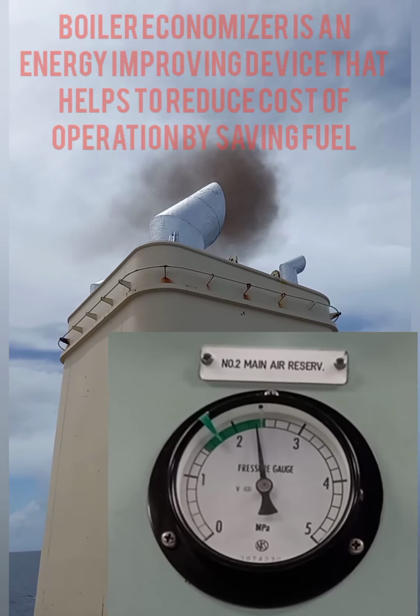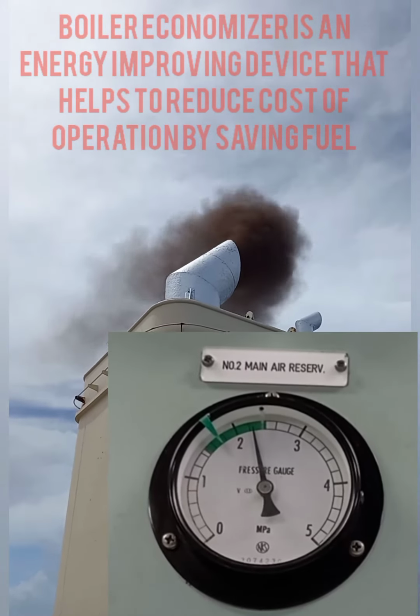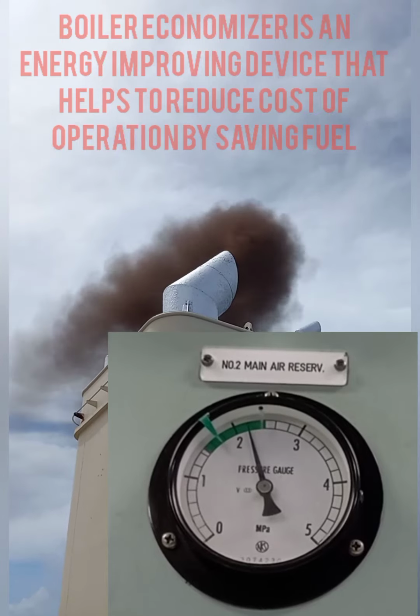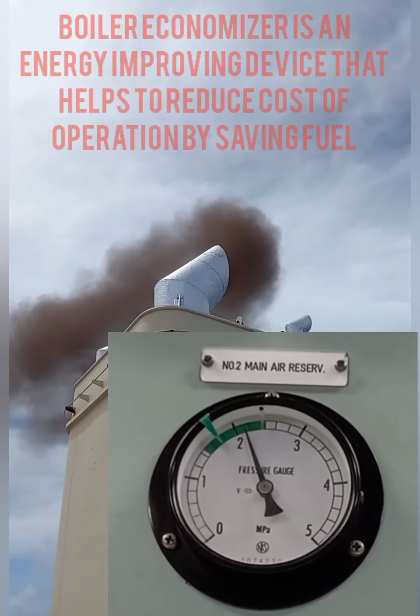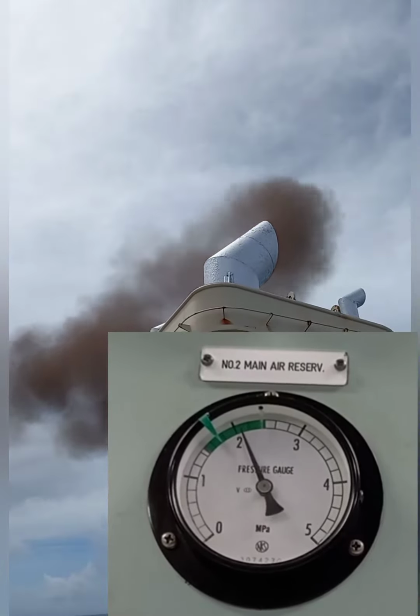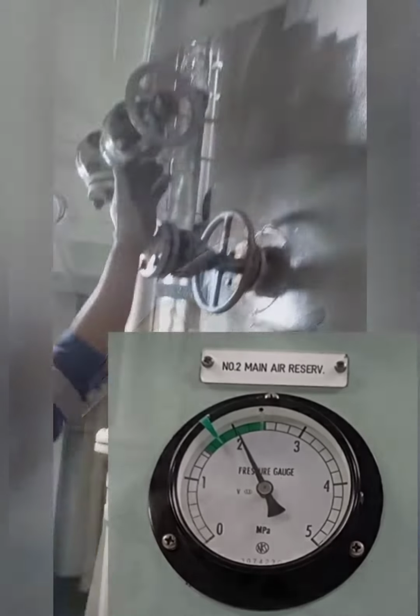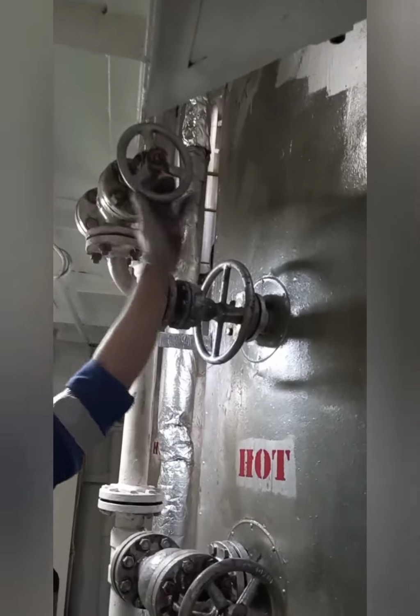The boiler economizer is an energy improving device that helps to reduce the cost of operation by saving fuel. Carry out soot blow at least once a day during voyage. The frequency and operation of soot blow will be based on the performance of the economizer.